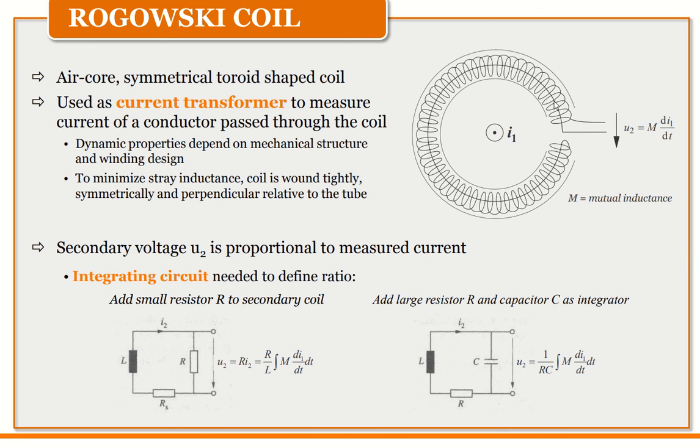Actually, the Rogowski coil you can design on your own, because it has a simple structure. Just loop the conductor wire on a small hole, or the pipe cable on the pipe. So you can use the Rogowski coil for your application, but there are still parameters that you need to characterize to know the efficiency of the sensor.